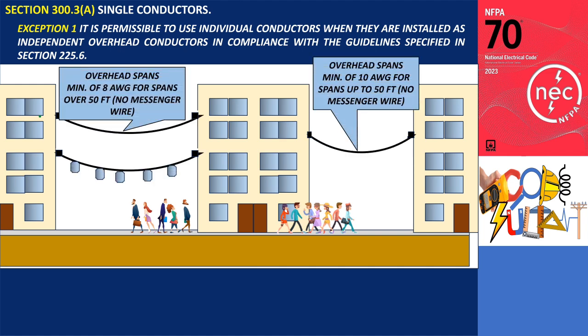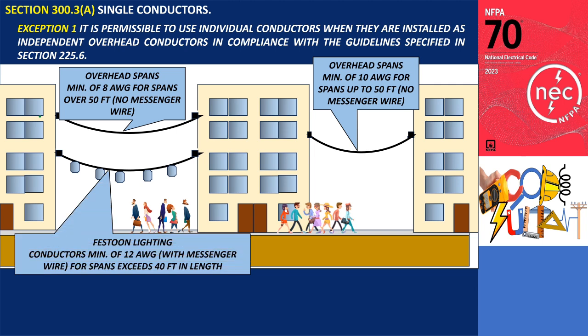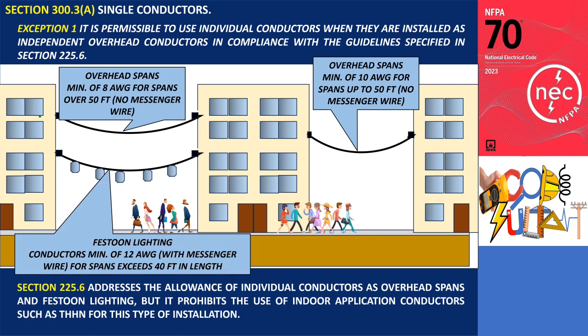Section 225.6 addresses the allowance of individual conductors as overhead spans and festoon lighting, but it prohibits the use of indoor application conductors such as THHN for this type of installation.